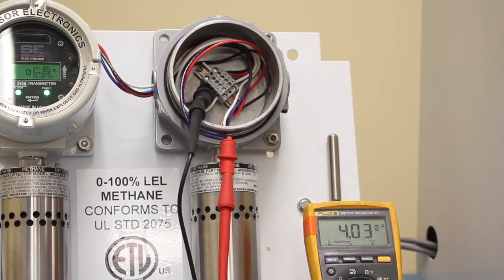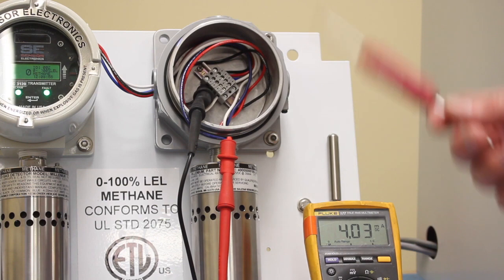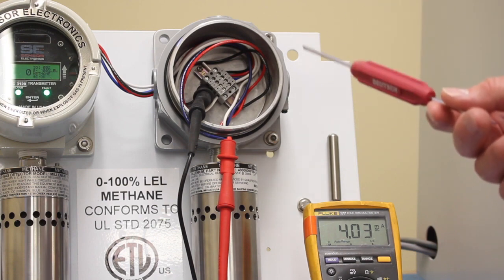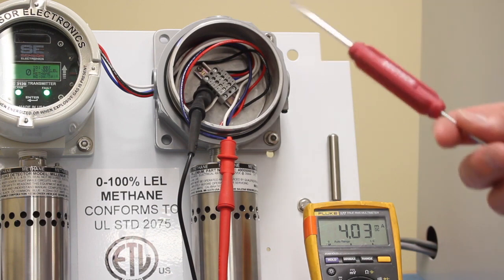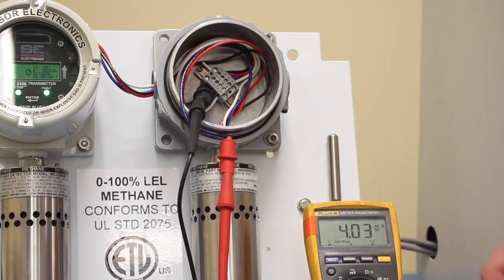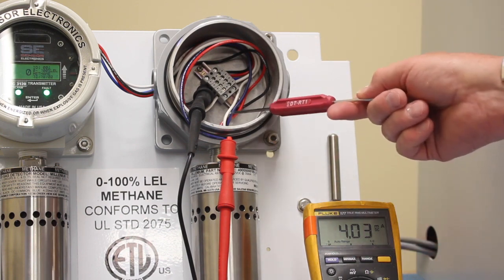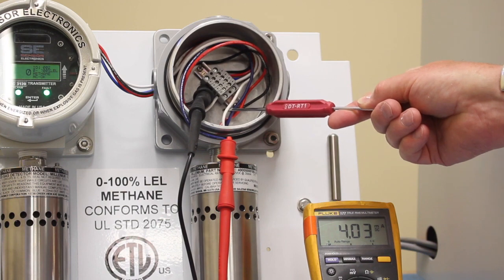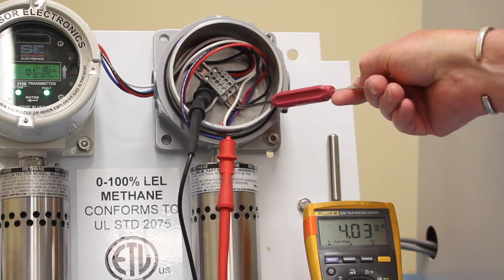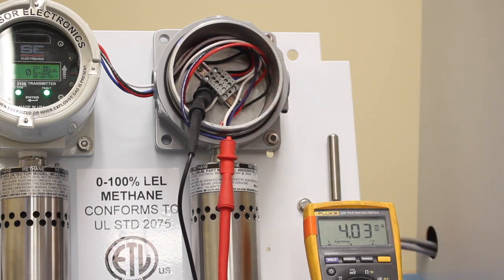Now the Millenium sensor has 4 wires coming out of it: a red wire for positive 24 volts DC, a black wire for negative 24 volts DC, a white wire, which is our calibration slash communication wire, then the blue wire, which is hooked up to the current meter, is the 4 to 20 milliamp output.